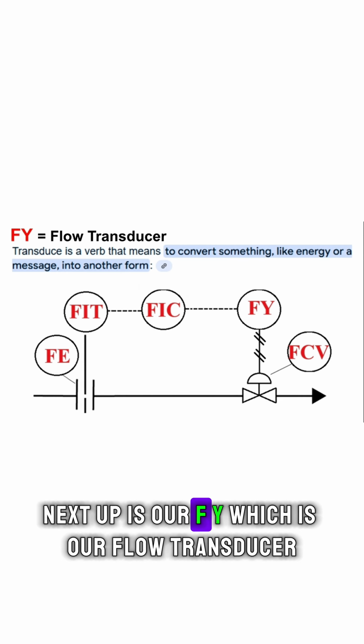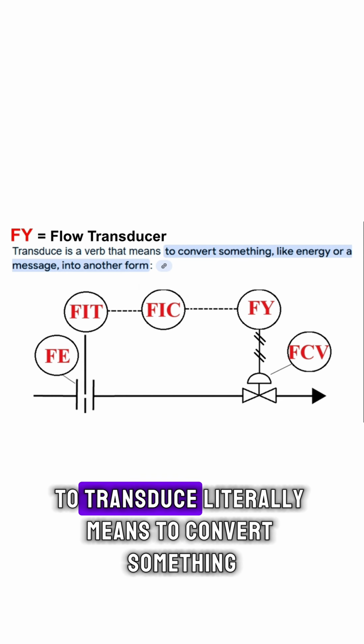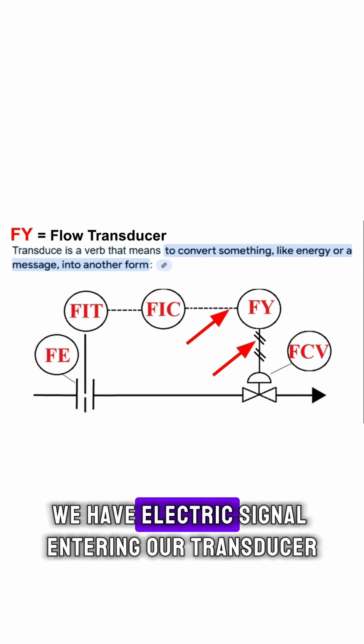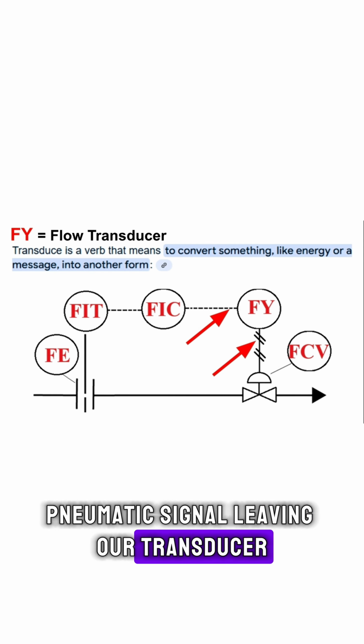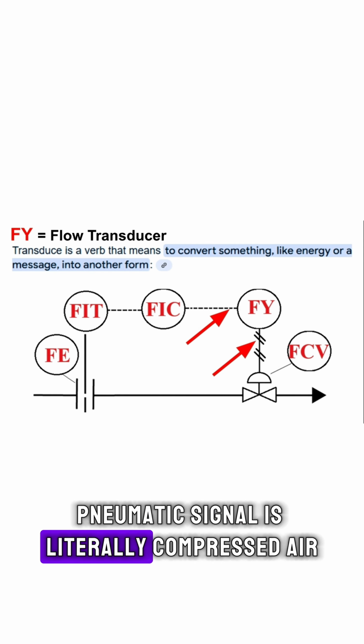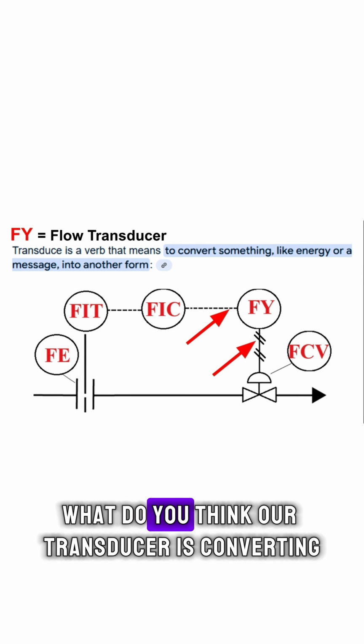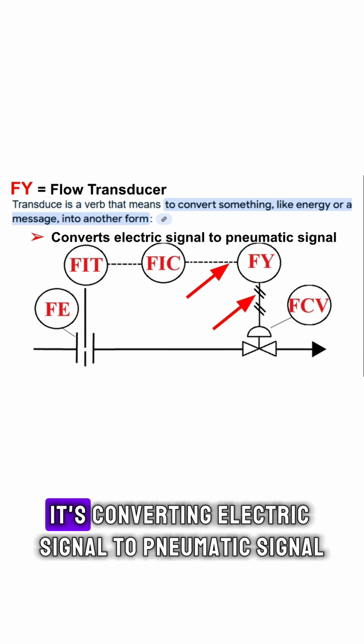Next up is our FY, which is our flow transducer. To transduce literally means to convert something. Well, we have electric signal entering our transducer and pneumatic signal leaving our transducer. Pneumatic signal is literally compressed air. So what do you think our transducer is converting? It's converting electric signal to pneumatic signal.